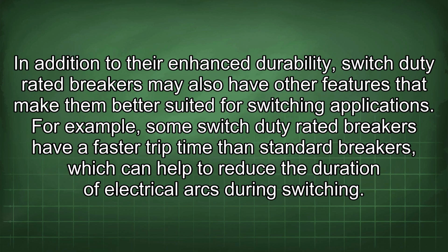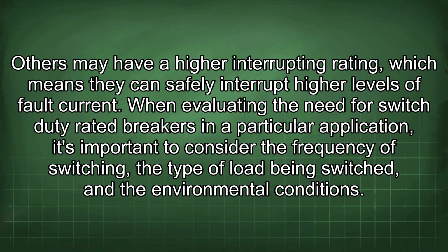In addition to their enhanced durability, switch-duty rated breakers may also have other features that make them better suited for switching applications. For example, some switch-duty rated breakers have a faster trip time than standard breakers, which can help to reduce the duration of electrical arcs during switching. Others may have a higher interrupting rating, which means they can safely interrupt higher levels of fault current.